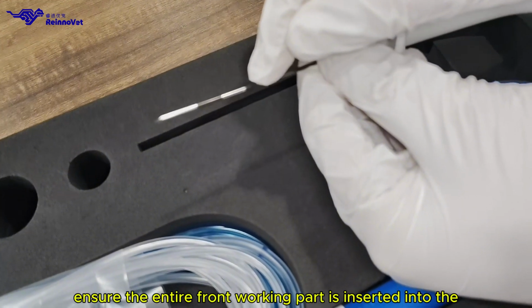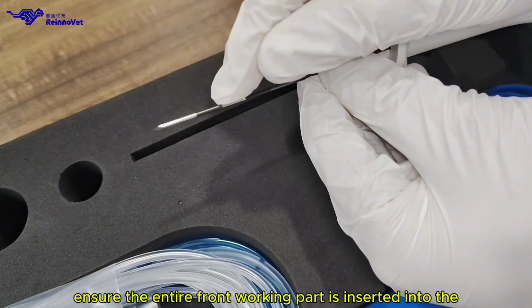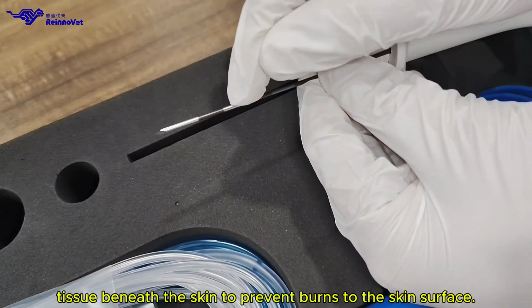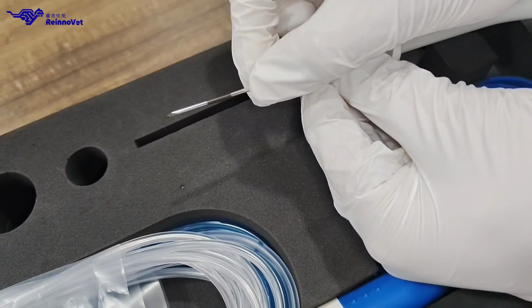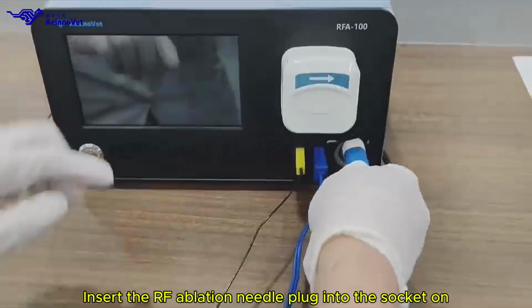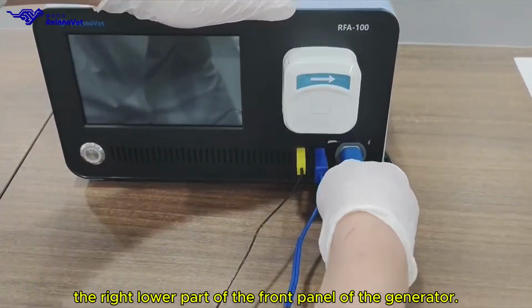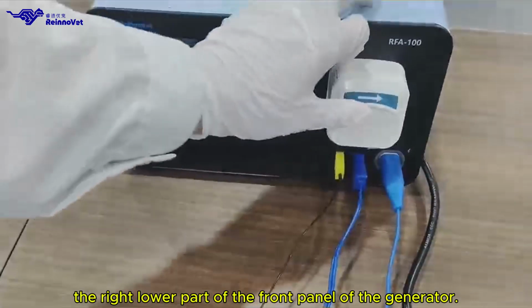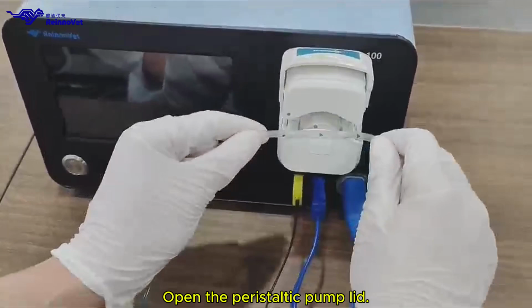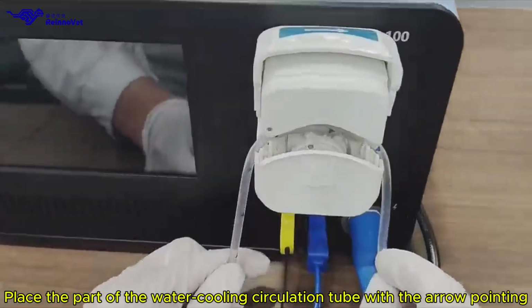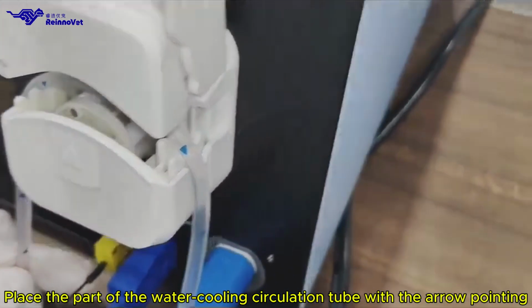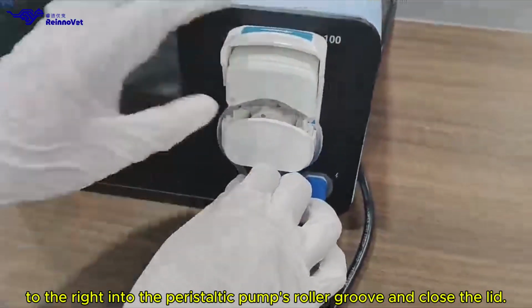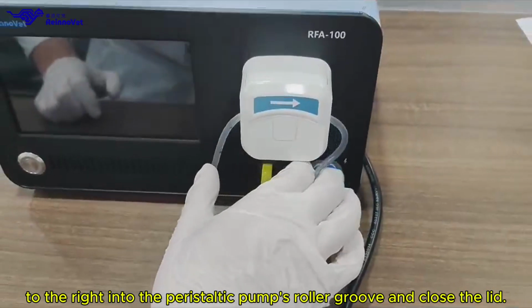During insertion, ensure the entire front working part is inserted into the tissue beneath the skin to prevent burns to the skin surface. Insert the RF ablation needle plug into the socket on the right lower part of the front panel of the generator. Open the peristaltic pump lid. Place the part of the water cooling circulation tube with the arrow pointing to the right into the peristaltic pump's roller groove and close the lid.